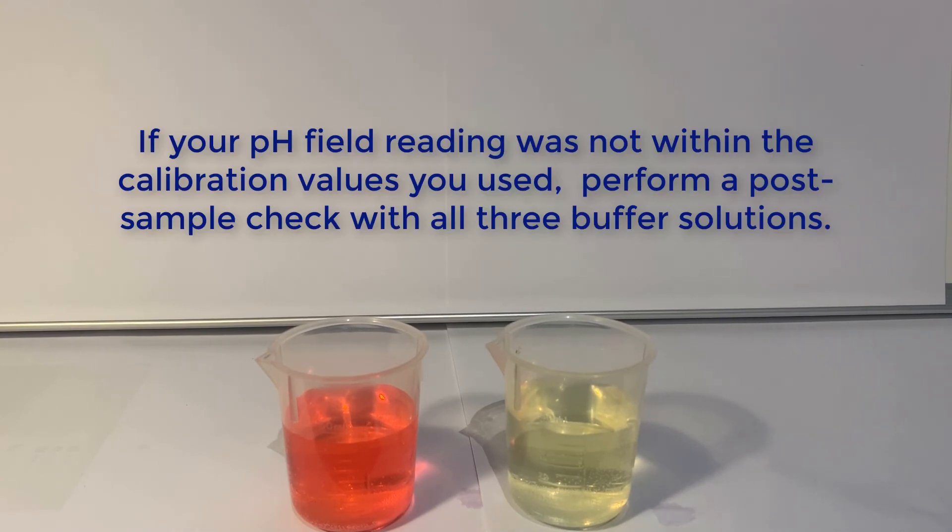If your pH field reading was not within the calibration values that you used, perform a post-sample check with all three buffer solutions.